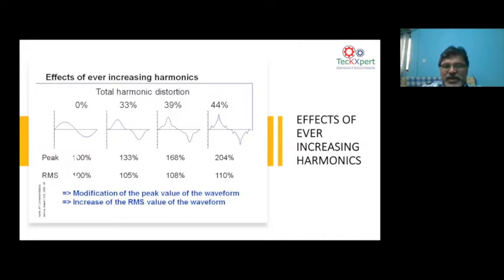The next. Now you can see this. When you have harmonics in the network, you see how the RMS current increases. With a 44% distortion in harmonic current, you will see the RMS current going up by 10%. That means your cables and equipment, which are all rated for a certain amount of current, you have to look into derating, because when the harmonics are in the network, you have a 10% increase due to the harmonic currents. That means derating is what is specific in this case. Go to the next.